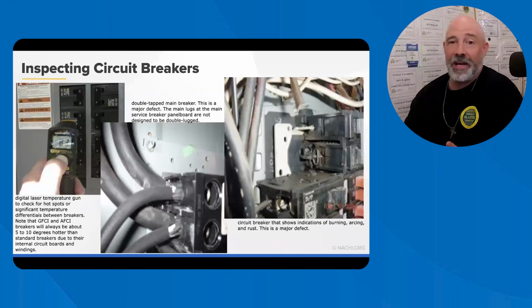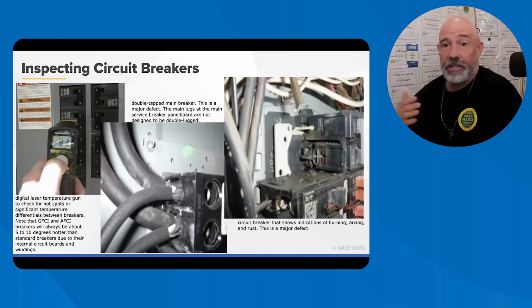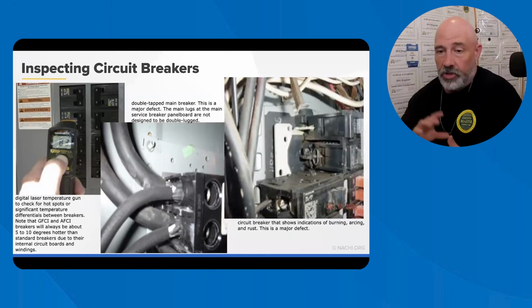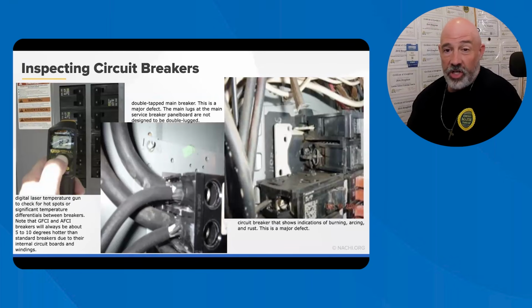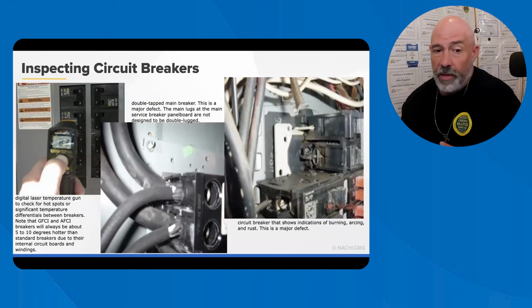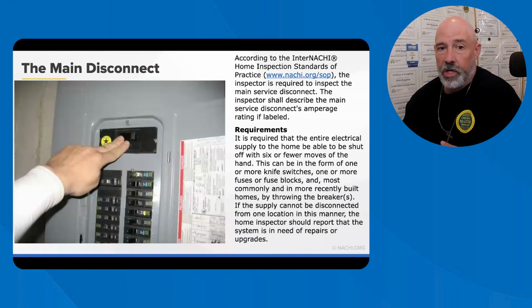Do the GFCI breakers test and reset properly? Like I said, twice a year, that's the way you do. Same thing with the AFCIs. You want to test them and make sure that they reset properly. Is there any signs of overheating? That's why I like to use a thermal camera, to make sure that the wires aren't getting really super hot. They are going to run a little hotter than the rest of the breakers because they are typically working. So if there's any signs of arcing or smoke damage or anything like that, you want to make sure you're calling that out.